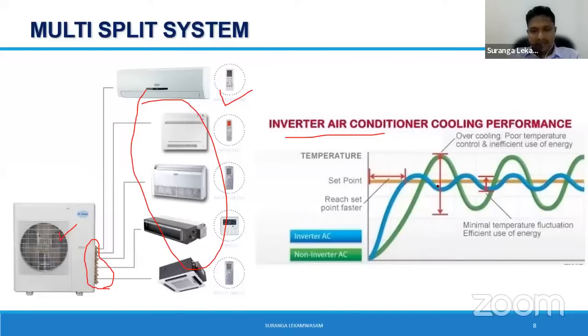Instead, if you run it on an inverter, where you load and unload the compressor according to the cooling demand, you can see your deadband is now narrowed. So your comfort level is much better. As well as, and this is something very important, inverter technology gives you much better efficiency simply because when the compressor runs at different speeds, mostly it runs in its efficient range, probably 70 to 90%. Any compressor is much more efficient in that range. So that is why you can claim much better energy efficiency in inverter technology, right?